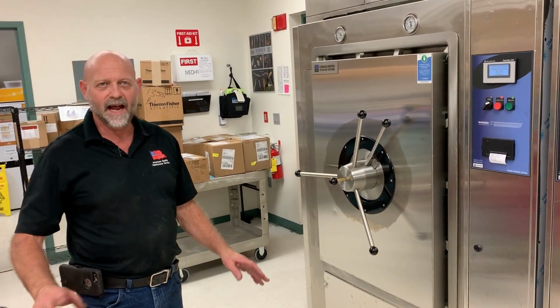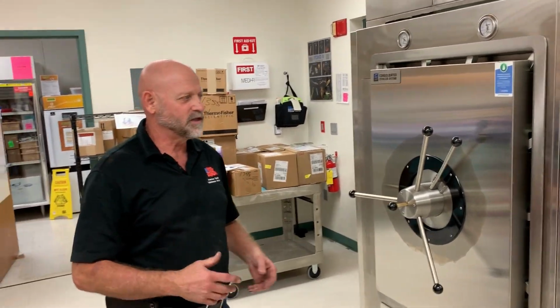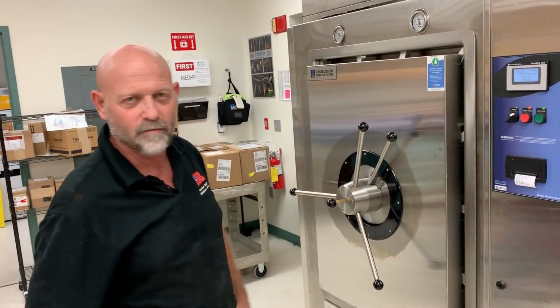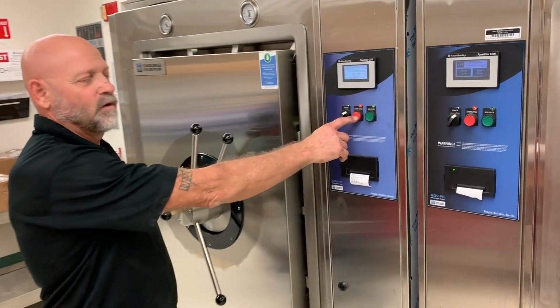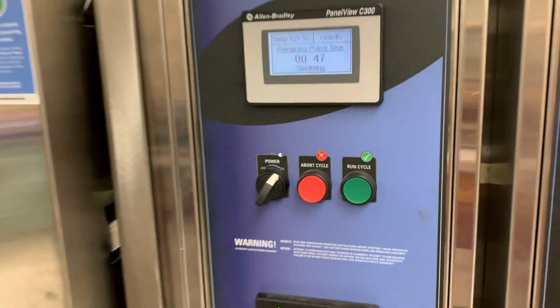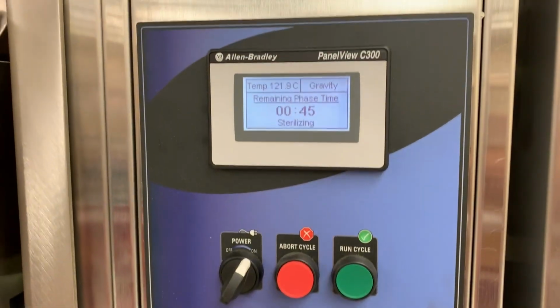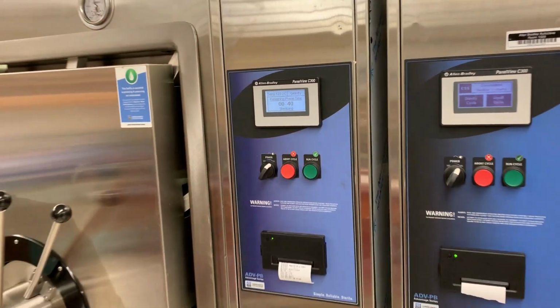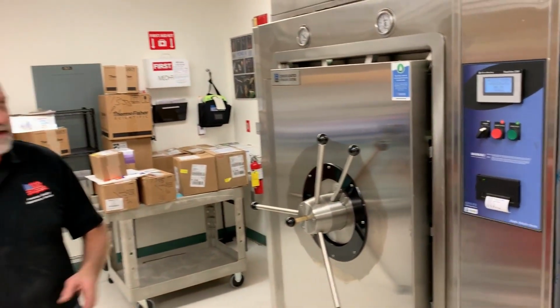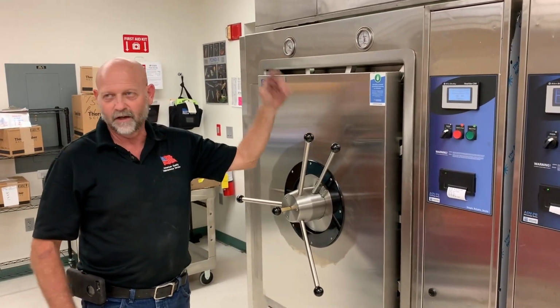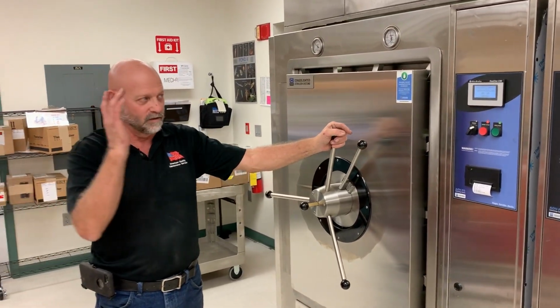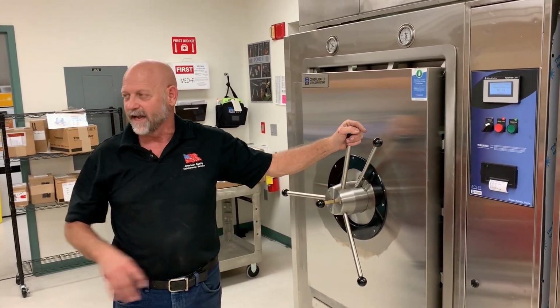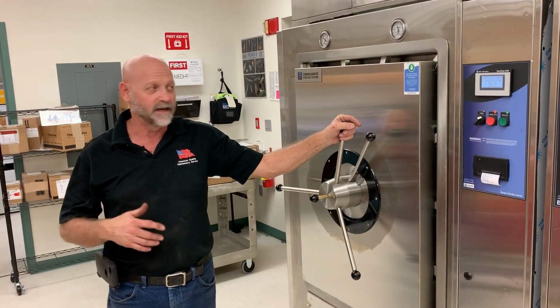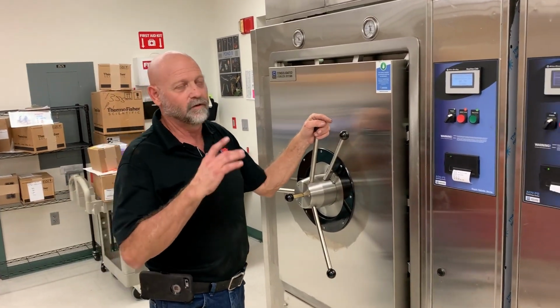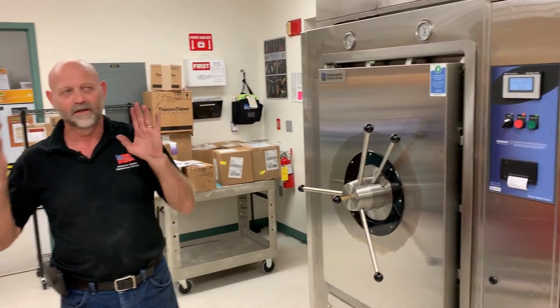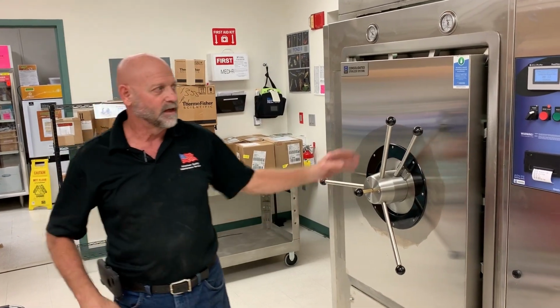Now, if at any time you have an emergency, there's a huge steam leak, there's anything like that, there's an abort button right here. All you have to do is press abort. It will follow its normal evacuation procedure. If it's gravity, it'll open up the dump valve, it'll evacuate the system quickly. If it is a liquid cycle, it will not. It will do a controlled evacuation.